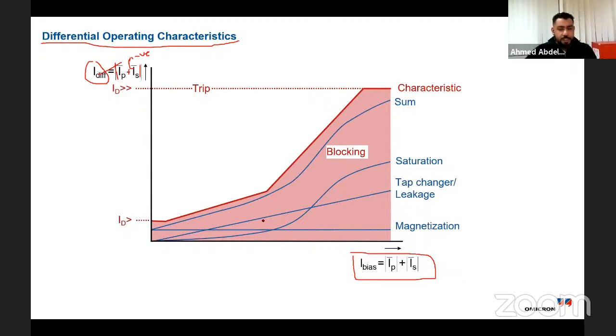What does this characteristic consist of? It consists of ID greater, which we said is the minimum operating current, which we define to avoid the main error of the CT ratio. And I have ID greater greater, we call it the unrestrained differential current. What does the word unrestrained mean? We will understand it right now.